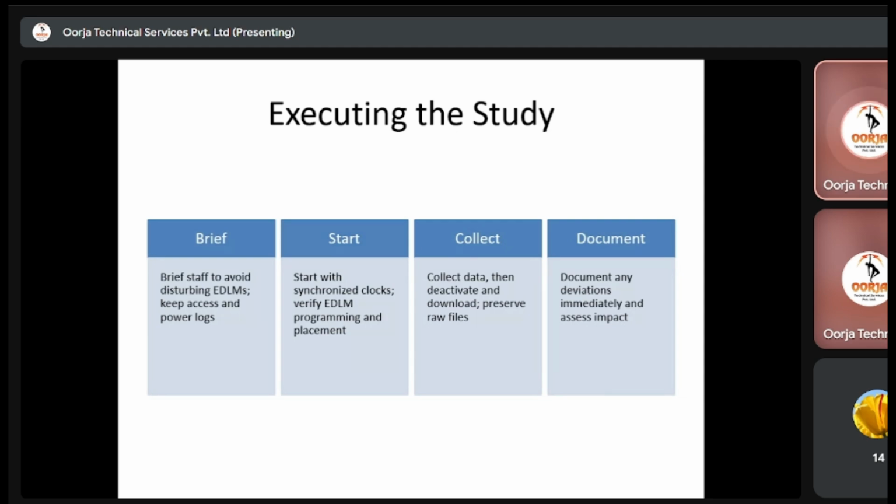If the data loggers are set to a 2 minute or 5 minute cycle, every data logger will have the same sampling time. So we should follow this. Otherwise, what will happen? The temperature recorded at a particular time instance will be different for all the data loggers.